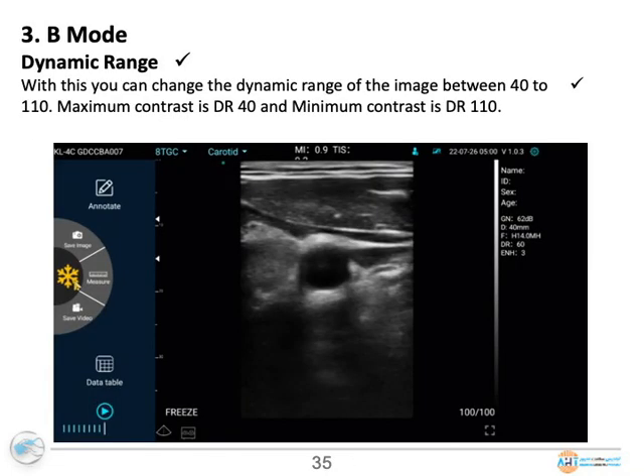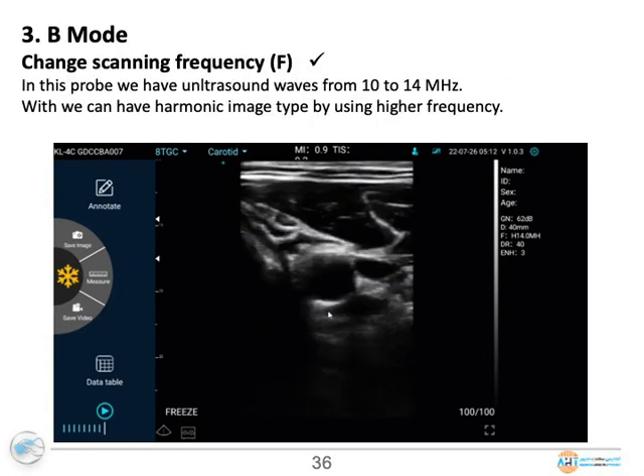Dynamic range. With this, you can change the dynamic range of the image between 40 to 110. Maximum contrast is DR40 and minimum contrast is DR110. B mode. Change scanning frequency. In this probe, we have ultrasound waves ranging from 10 to 14 megahertz. With this, we can have a harmonic image type by using a higher frequency.